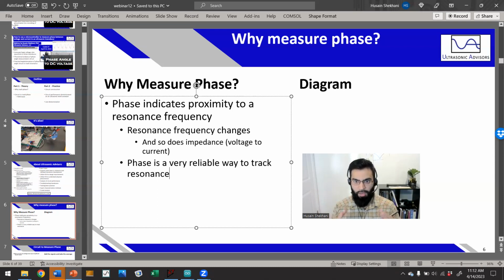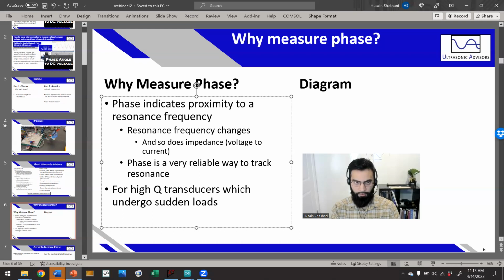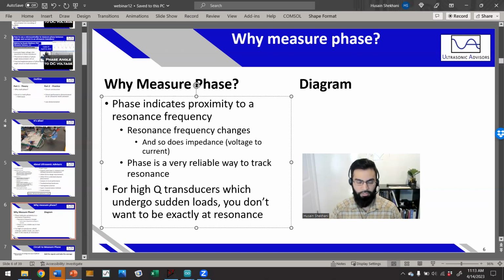For many high-Q transducer applications that undergo sudden loads, you don't want to be exactly at resonance, or anti-resonance for that matter. Anti-resonance is a bit more lenient, but I'll focus on resonant frequency since that's more utilized and practical for most applications. You don't want to be exactly at resonance because once you get loaded, or the frequency changes, you get a huge drop in your current value and operating conditions.